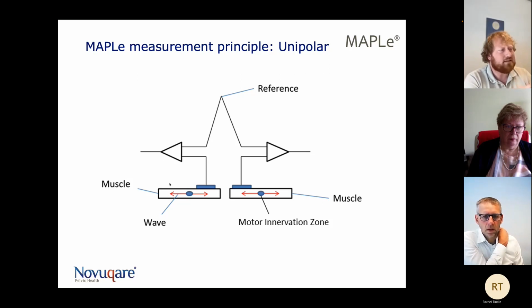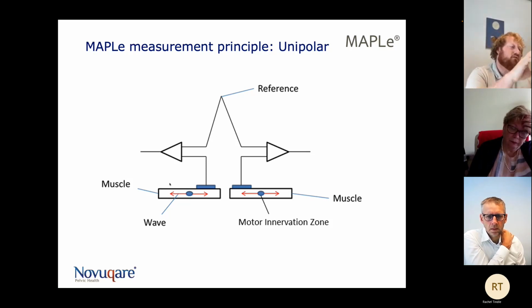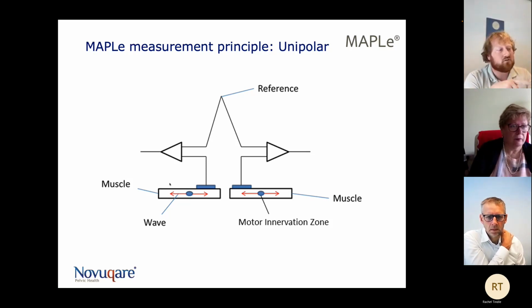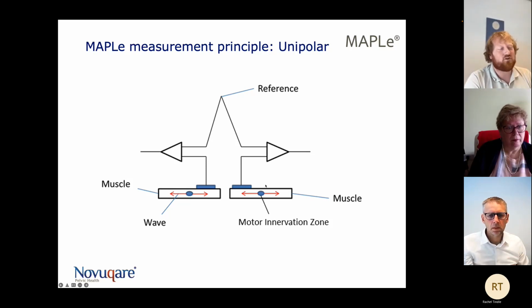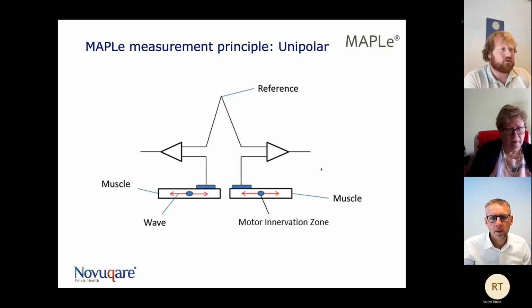When it's inserted, we have the reference electrode for the zero potential of the body, and then the activity of each individual electrode is compared to that with the average of the total active electrodes. It's a very technical description, but when we start a measurement, we first set the zero potential of the body by using the reference electrode. Then each individual electrode takes a measurement according to that. And then the baseline EMG within the pelvic floor is the average of all active electrodes of the probe.